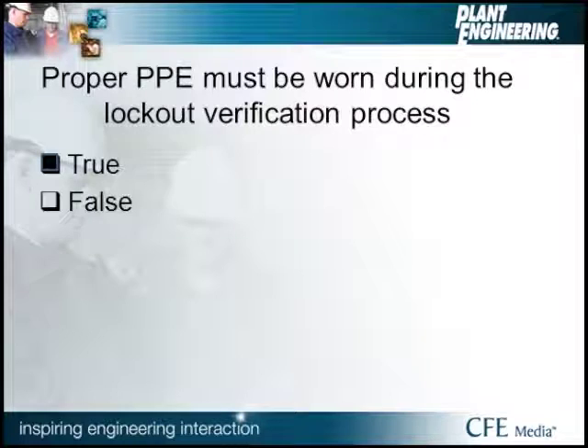Proper PPE must be worn during the lockout verification process. It's true. You don't know if that equipment is shut off just because you've thrown the handle. All you know for sure is that the handle moved. Got to test it out.